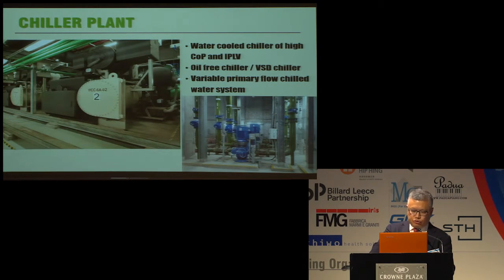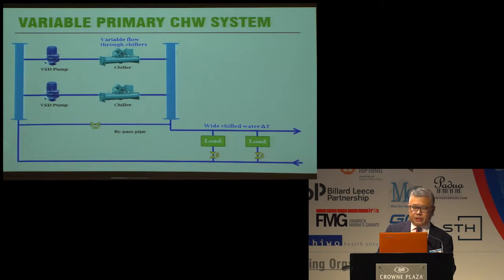Now, conventionally, central chiller plants are designed with primary and secondary circuits where the secondary pumps provide variable flow to the building, and primary pumps maintain a near constant water flow through the chillers. Now, modern chiller design makes variable water flow through the evaporators possible with a variable flow chilled water system. So the system can reduce the installation and operating costs because one group of chilled water pumps is eliminated. Further cost reduction in pump energy can also be realized by adopting a wider chilled water delta T.